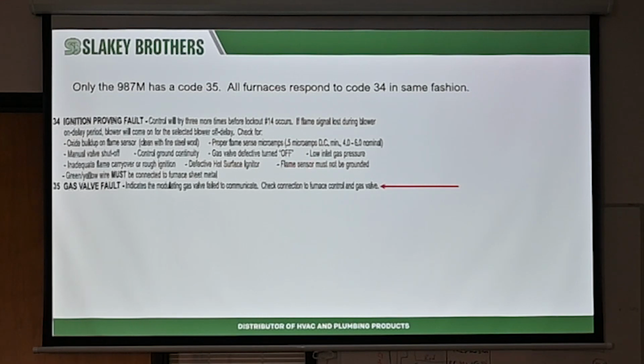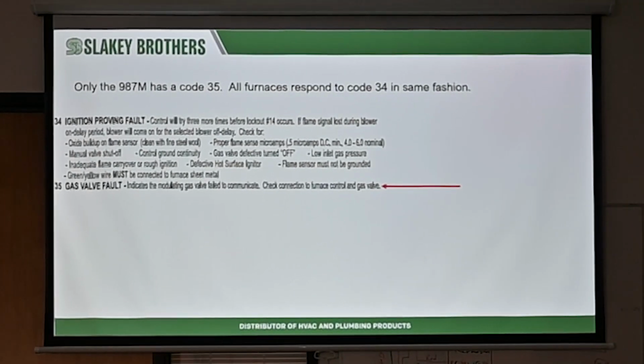So, the flame sensor must not be grounded. That little rod, as it bends in, maybe by accident at the factory or whatever, it got bent and it's touching metal. Make sure it's not touching metal. The wire, again, make sure it's not touching metal. Otherwise, that's going to affect it.